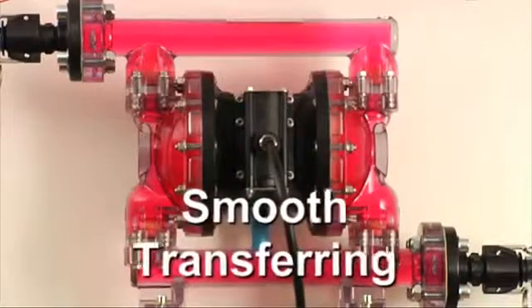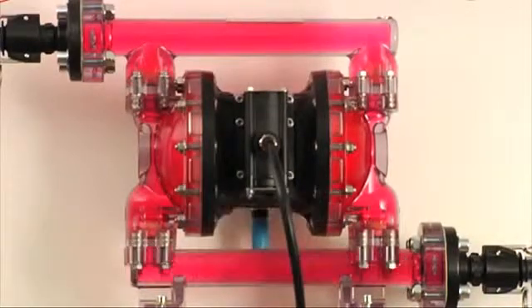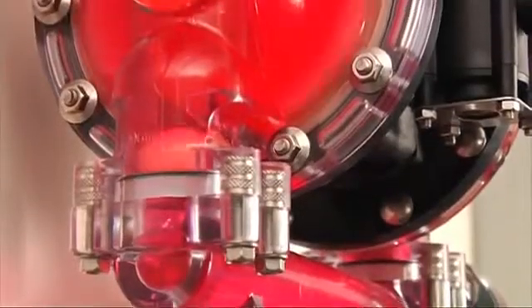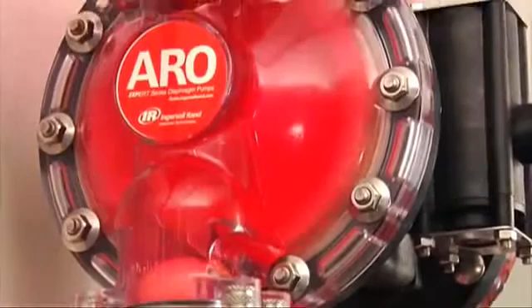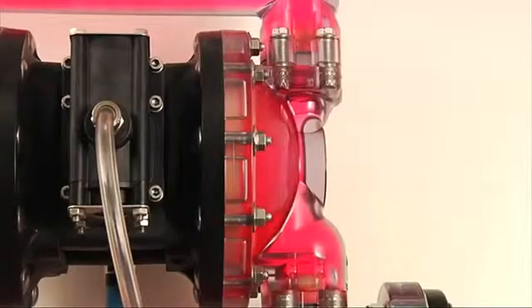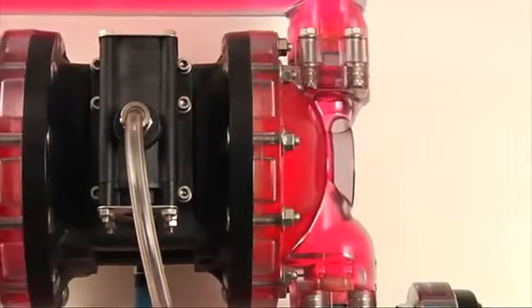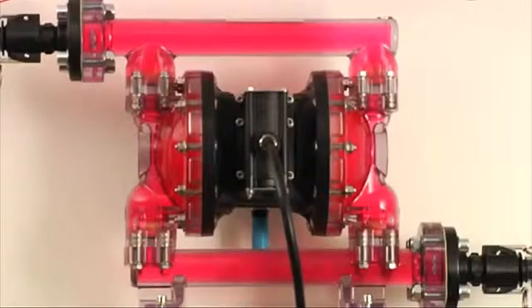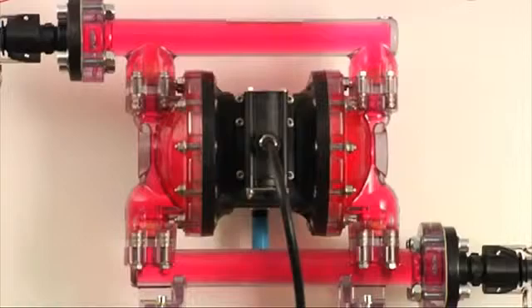An air operated diaphragm pump is designed very simply with two fluid chambers. Each chamber has two ball valve checks. One of the valves admits the media being pumped to the diaphragm chamber, and the other allows the material to exit the diaphragm chamber. This very simple device will ensure a smooth transfer. Product will be moved from one place to another without froth or medium separation. This means for complex chemical processing, material will not foam or not be damaged by particle splits.